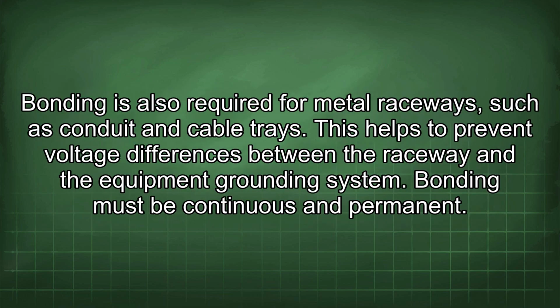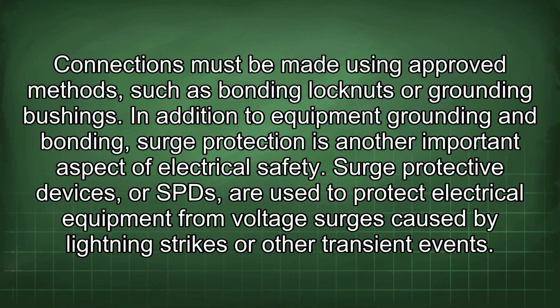Bonding is also required for metal raceways, such as conduit and cable trays. This helps to prevent voltage differences between the raceway and the equipment grounding system. Bonding must be continuous and permanent. Connections must be made using approved methods such as bonding lock nuts or grounding bushings.